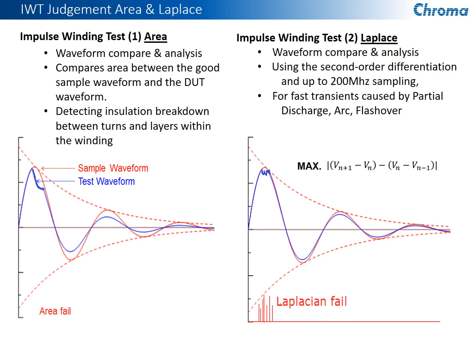So just a couple more examples of this. A normal good waveform that you see here in red, compared to a device under test that has a failure, such as a shorted turn, would give you a sudden change in the waveform, but you can also see it changes the area of the waveform during the ringing portion. So you'd be able to look at a large portion of the waveform and do this type of area comparison to give you good results in determining that your device under test is either passing or failing.